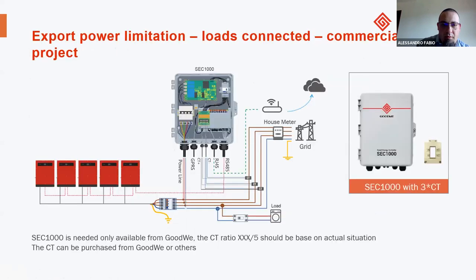Another option that we have is for export power limitation. This is more for a commercial rooftop project. It's the SEC 1000. It's an option that we use for export limitation to manage the three-phase system inverter. The idea is to measure the loads to the grid and set the consumption, so a zero feed-in concept, like other competitors, for example.